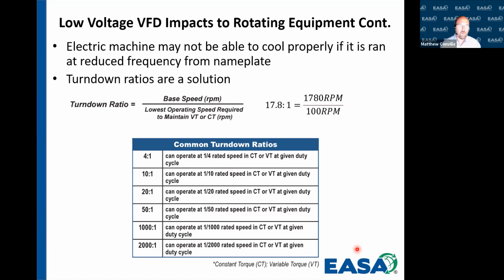So whenever we started seeing issues with rotating equipment, the motor manufacturers started creating motors that were inverter specific that had what they call a turn down ratio.